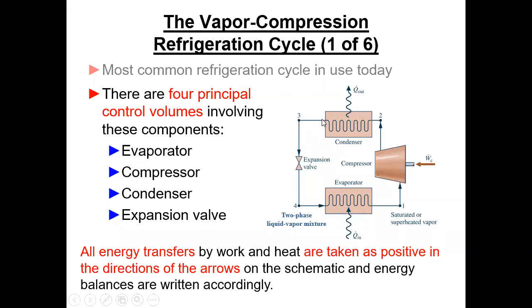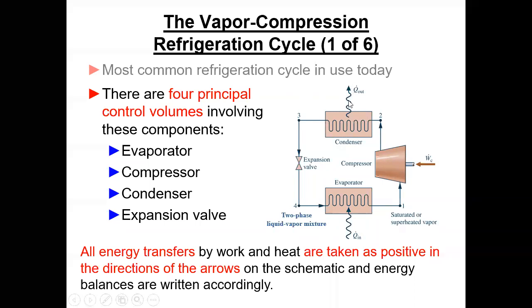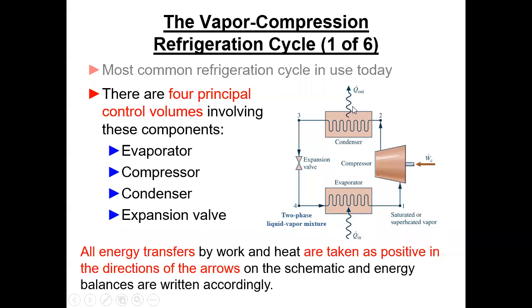We have to condense the refrigerant to the liquid state. Coming out of the compressor it's pretty warm — this could be 150, 175 degrees — so we don't have any trouble transferring heat to the outside. Some units have two boxes, one inside and one outside; some are all outside. This is your condenser coil and it's pretty hot — you probably don't want to put your hand on it. We just blow ambient air across there and blow that heat away.